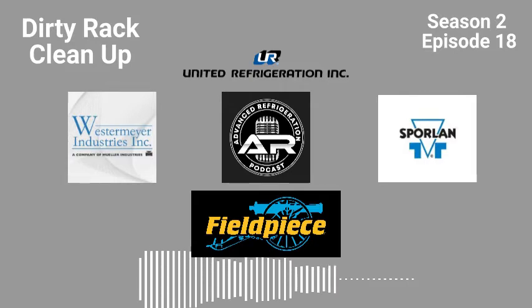Especially if you got a dirty rack. This is where I usually see these racks get out of control with the bypass filters. It's plugged, so it's bypassing. It's not doing its job anymore. So it's bypassing that oil in there, and that oil is dirty. Next thing you know, now it's plugging up all your screens.